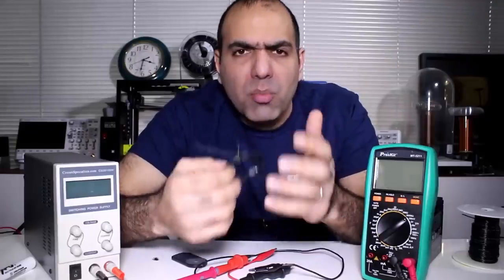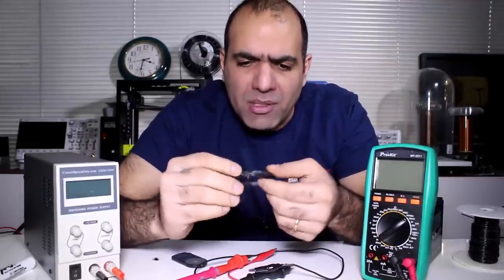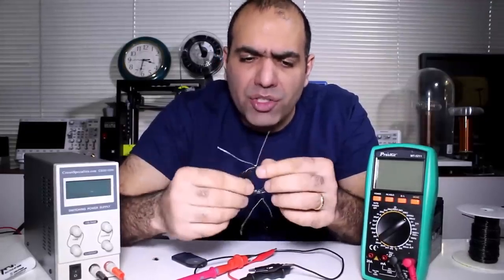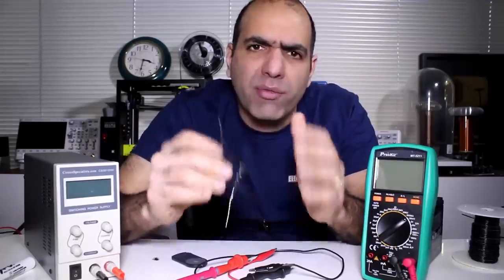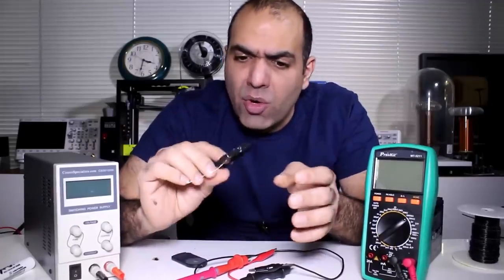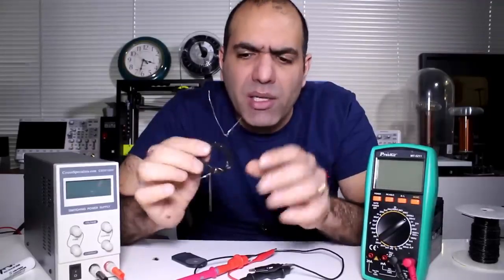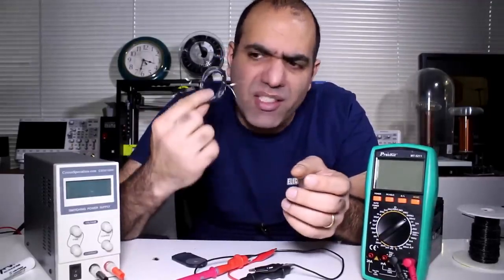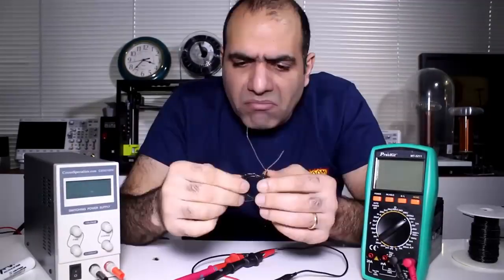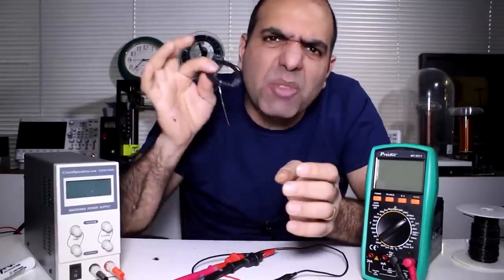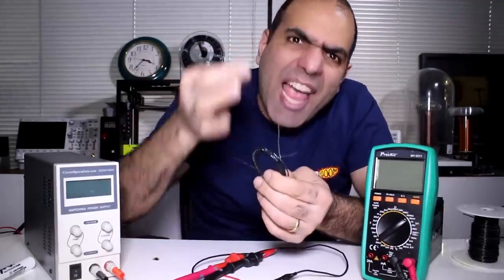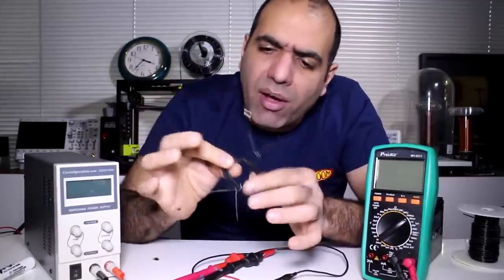I like to be able to measure higher currents, like 10 amps. But using this, the voltage drop would be 1 volt, which is too high for lower supply voltages. So in order to get the same 100 millivolt drop, I have to change the resistance of my shunt to 10 milliohms. It's simple. I can still use the same shunt and just inject the current and read it at 1/10 length of this wire.